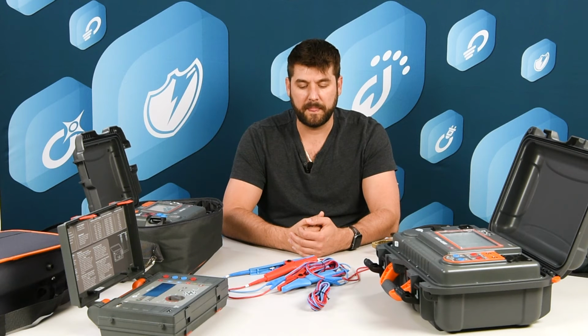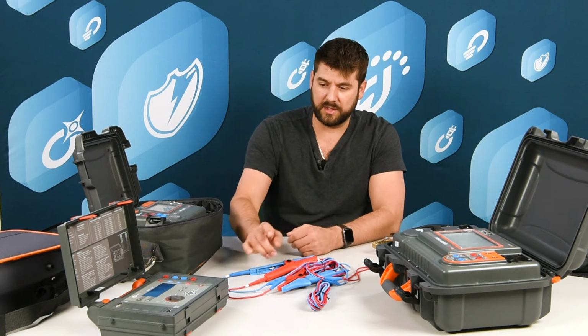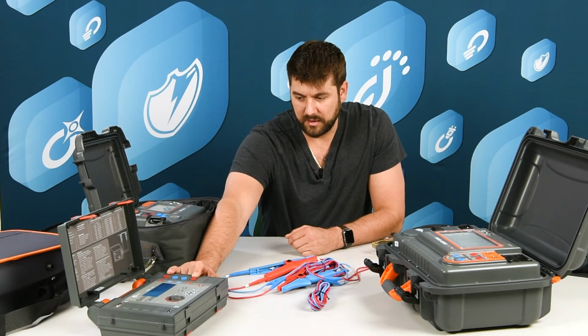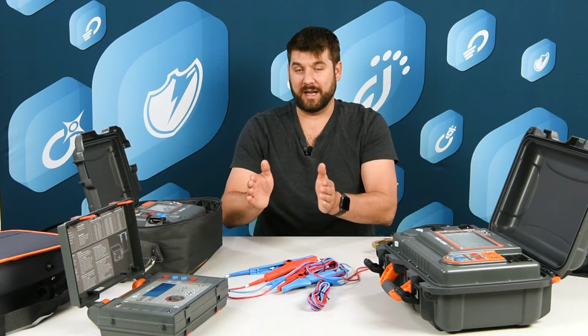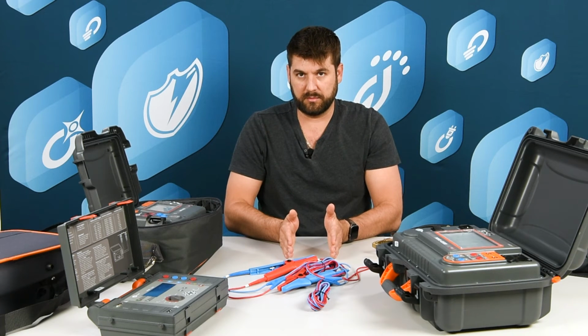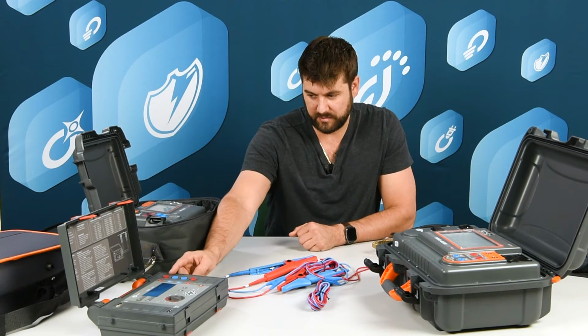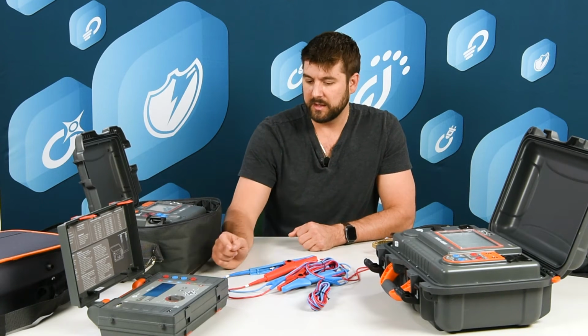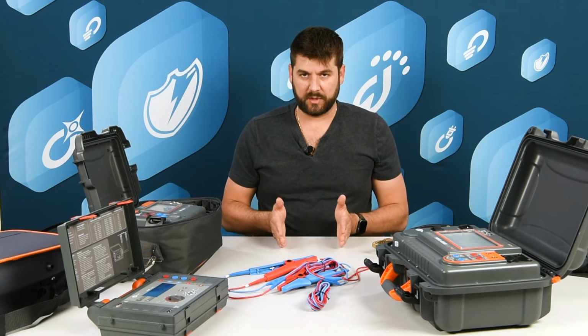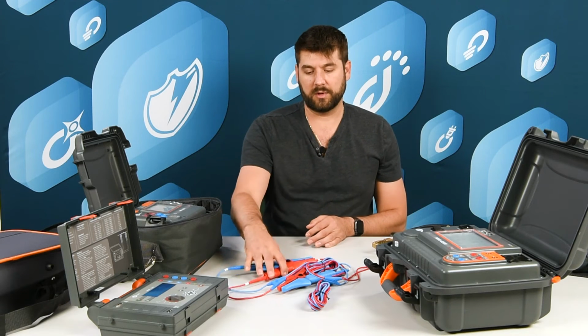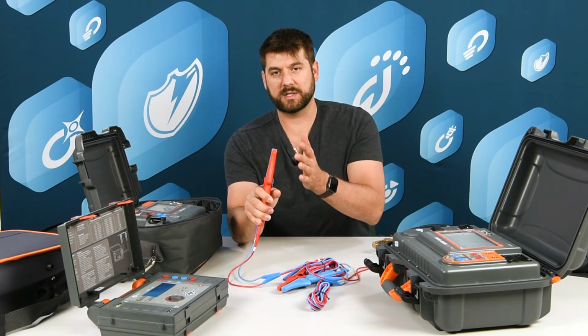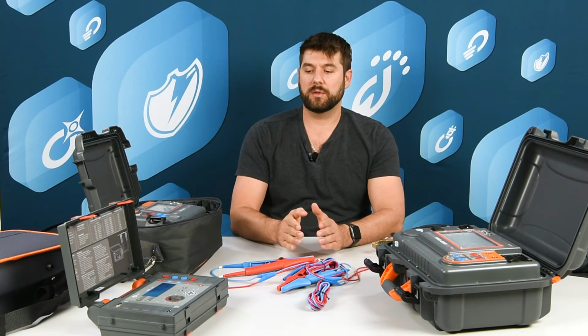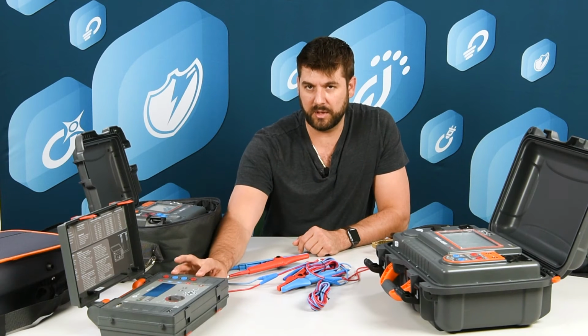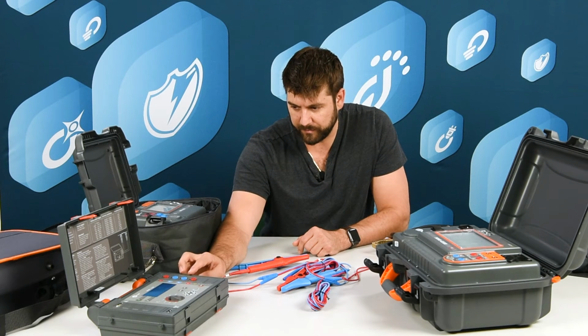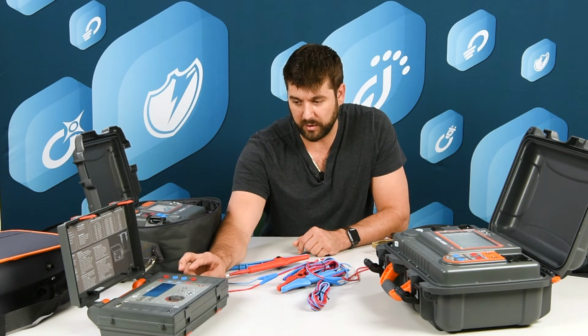It's very simple though. But something important to note is that your current leads need to be on the outside of your voltage measurement leads. It's laid out here pretty simply, you can see. So you want to make sure the voltage probes are inside of the current probes, or like they're set up on here, they're right together in the same place. But the resistance that you're going to measure is going to be from the point to point of where you put the voltage probes.